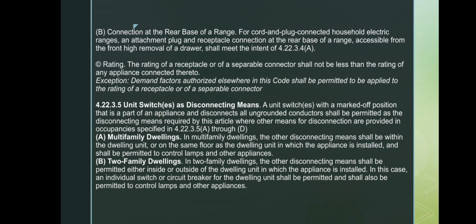The receptacle or connector used must have a rating that is not lower than the rating of the appliance connected to it. However, demand factors allowed in the code may be applied when determining the required rating.